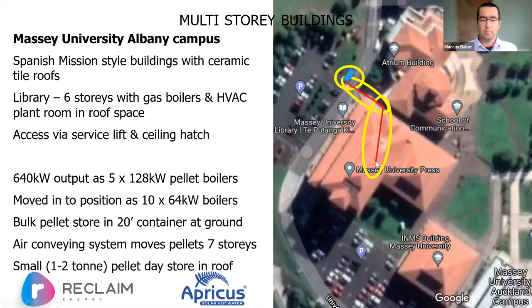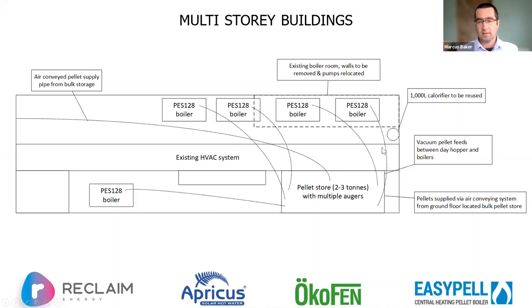And so we'd have a small one ton or so pellet store, basically as big as we can get away with for the structural guys, so that we've got, you know, maximum resilience up in the plant room. But that would be our kind of day hopper, you could call it. And then they would transfer in the completely standard way to each boiler. So if we just look in the plant room, there's already this huge HVAC system that takes up a good two-thirds. It's maybe not quite to scale, but it takes a good two-thirds of the room up here. And there's some other tanks and various things.